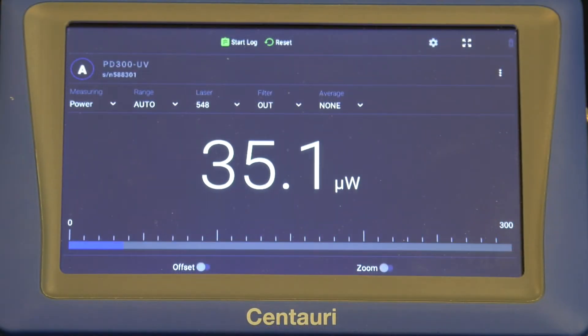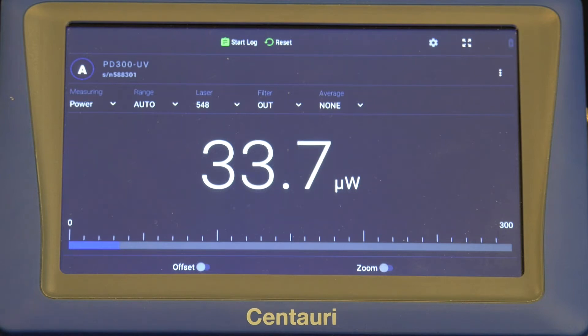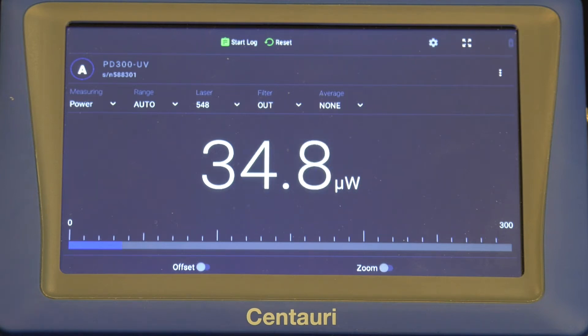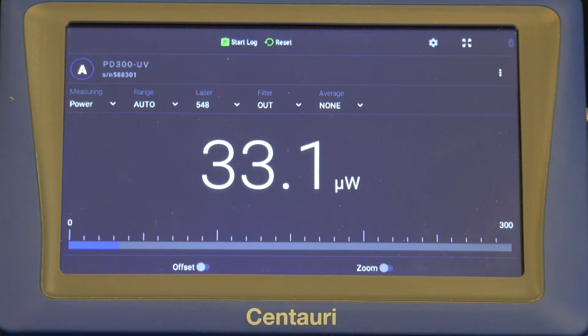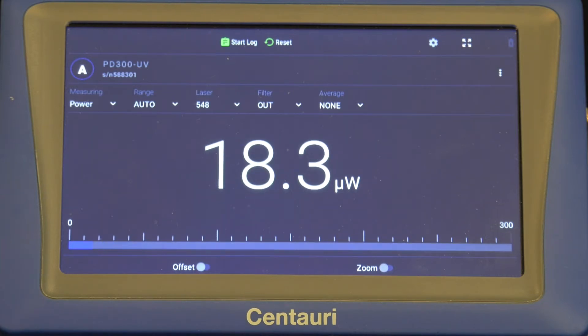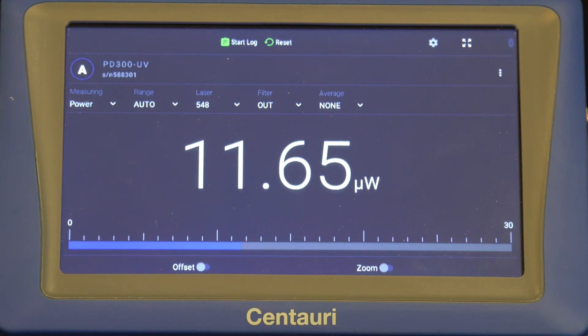Also, if it's in the middle of measuring and the signal increases to more than 100% of the range, it automatically moves up a range. And if the signal drops to below a certain percentage of full scale, it automatically moves down a range. It's very convenient. However, sometimes it can do funny things. Let's look at two interesting cases that we recently dealt with.